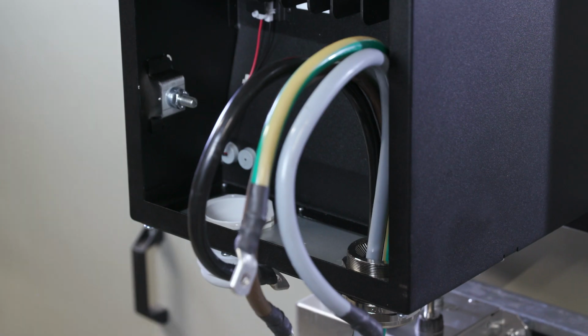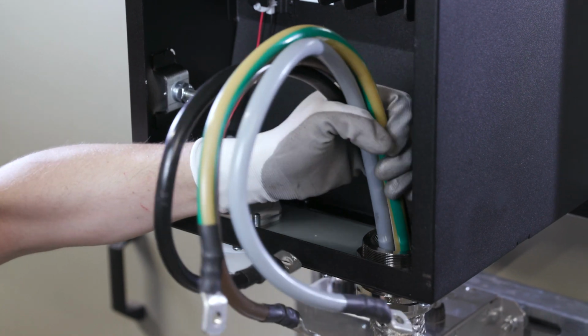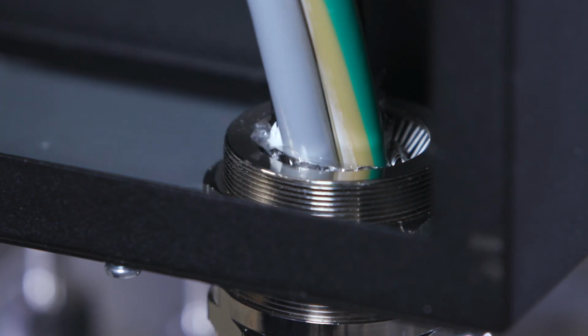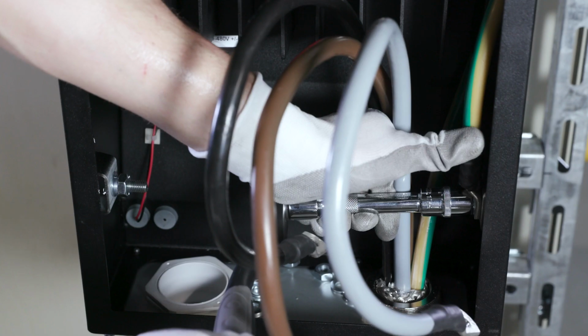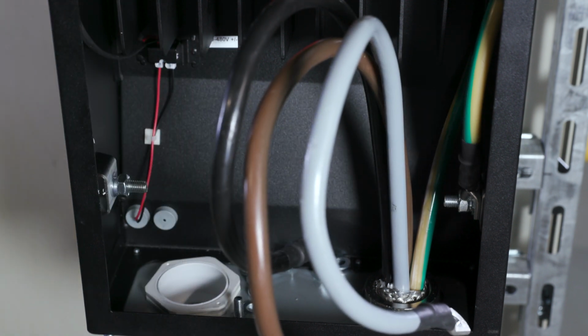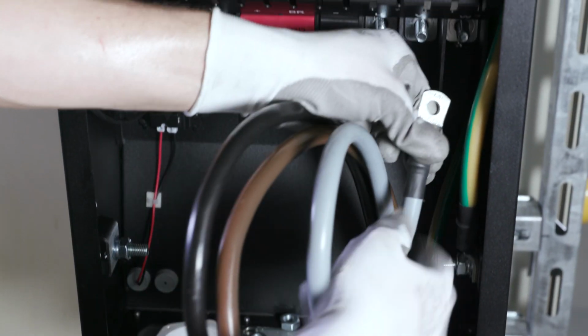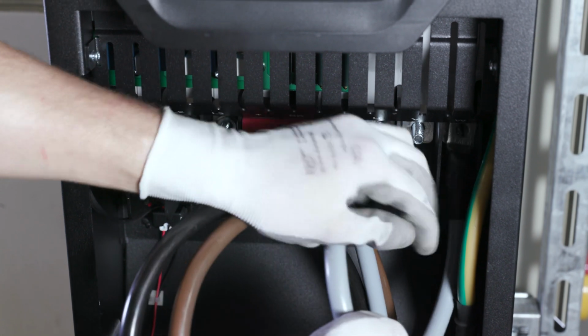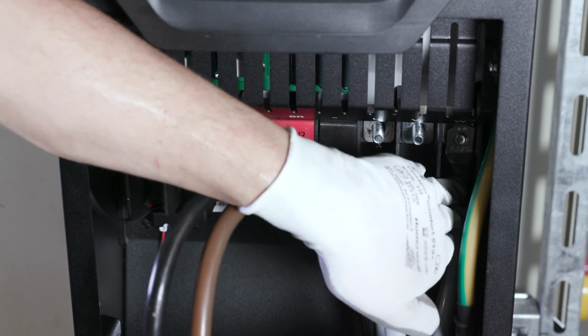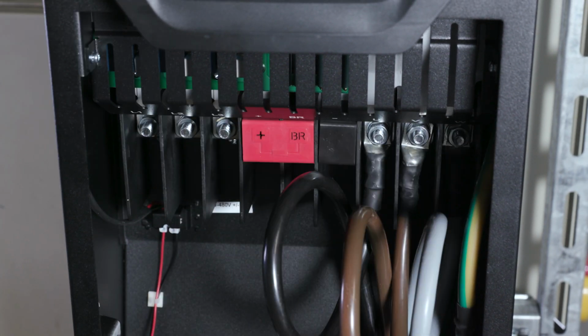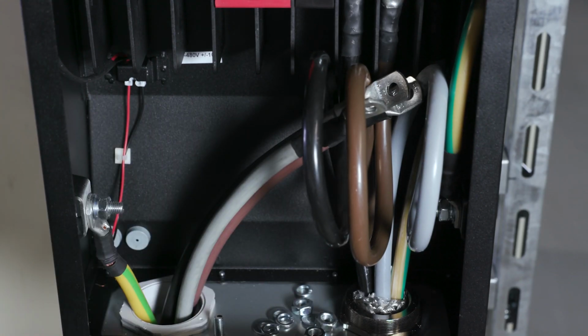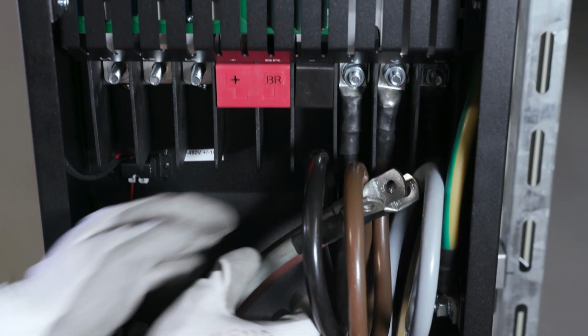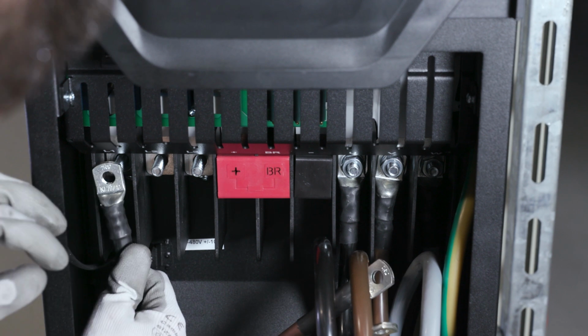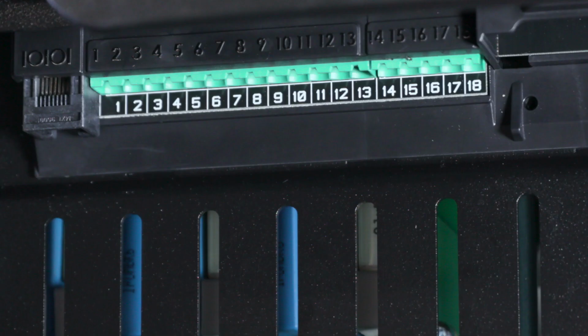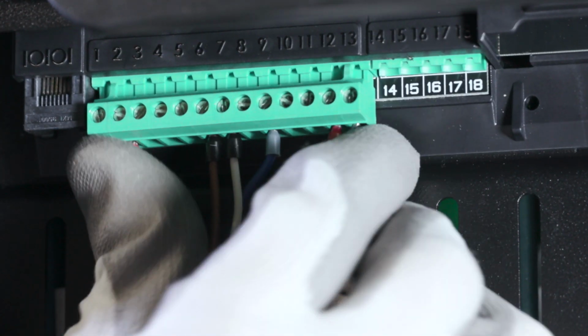Guide the motor cable through the EMC cable gland so that the shield is in contact with the EMC cable gland. The connection torques for the individual cables that connect to the VARIPACK can be found in the operating instructions, which you can download free of charge from the BITZER website under Electronic Components. For the motor cable, the voltage supply cable, and the control cables.